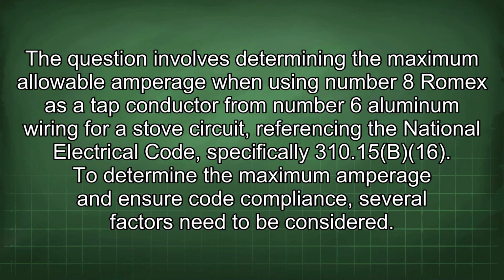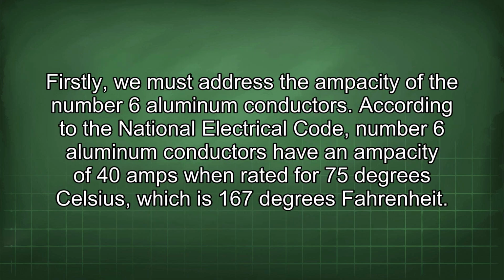The question involves determining the maximum allowable amperage when using number 8 Romex as a tap conductor from number 6 aluminum wiring for a stove circuit, referencing the National Electrical Code, specifically 310.15(B)(16). To determine the maximum amperage and ensure code compliance, several factors need to be considered. Firstly, we must address the ampacity of the number 6 aluminum conductors.